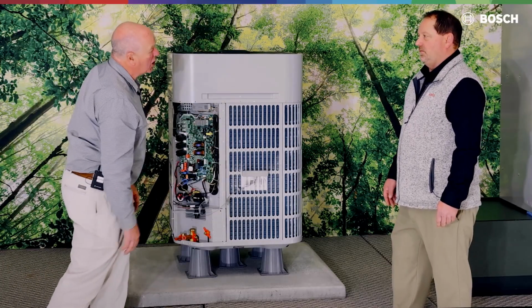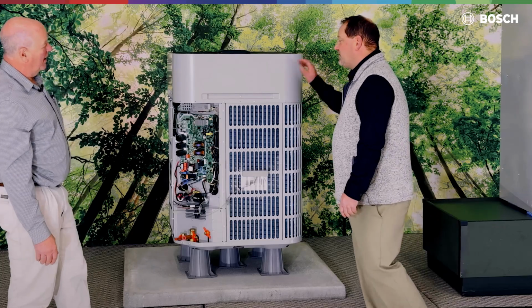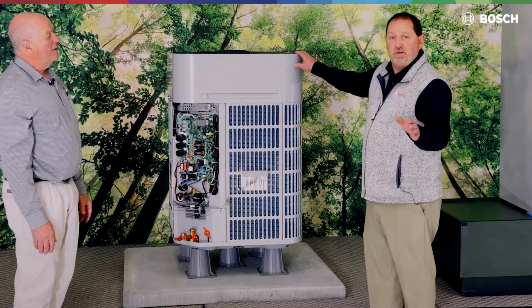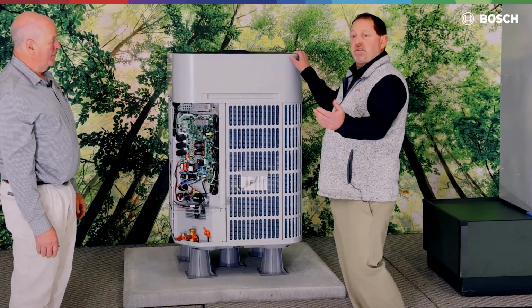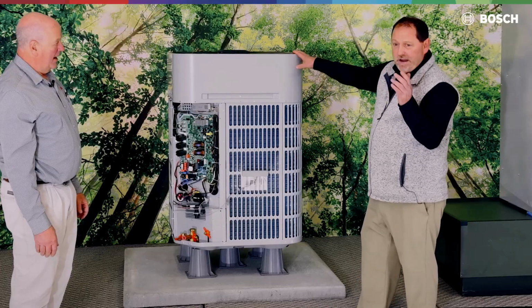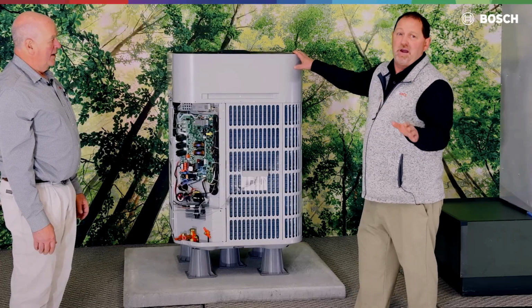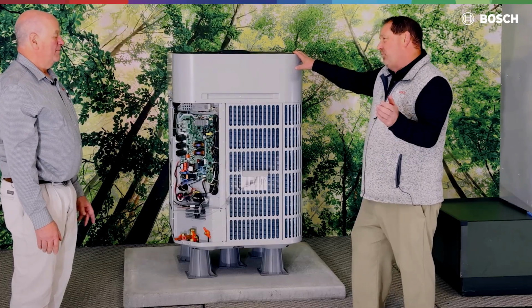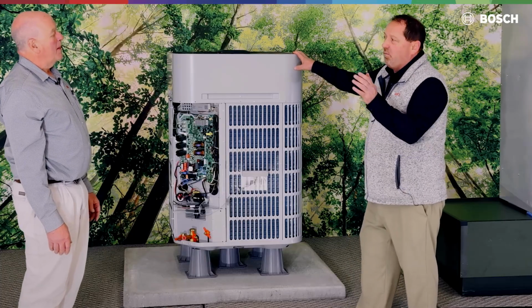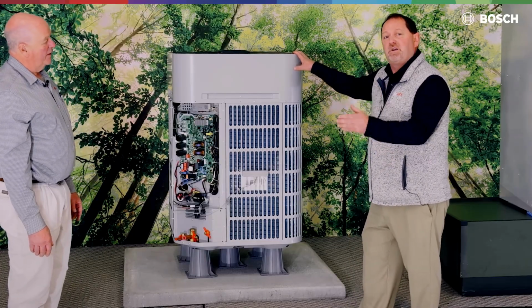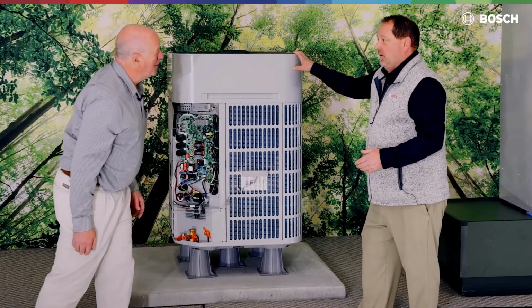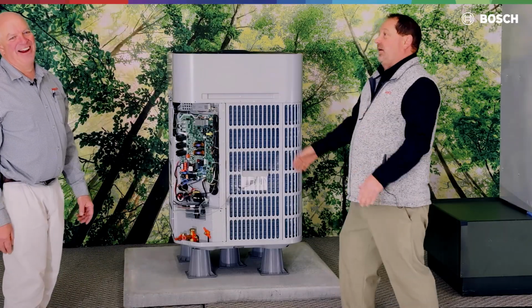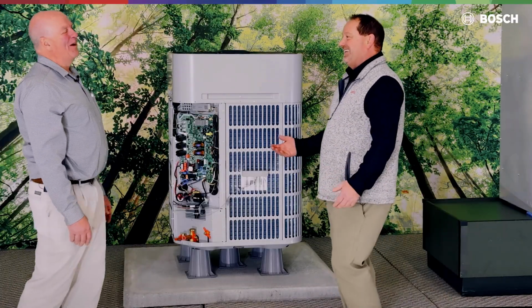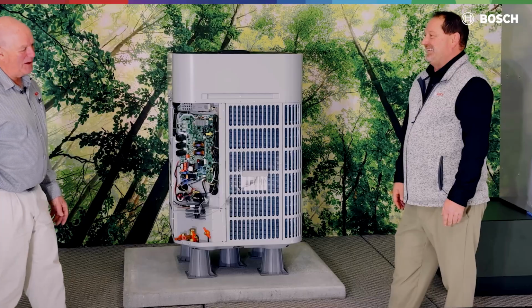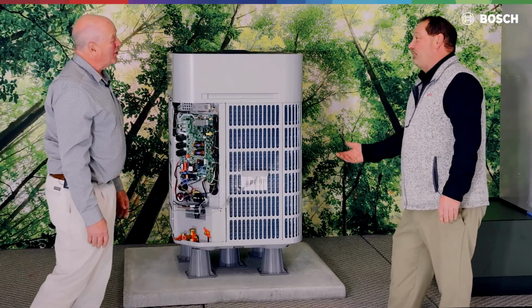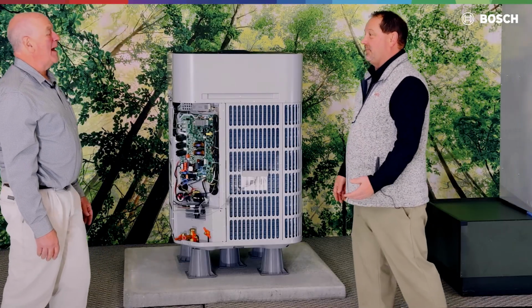And Chris, what is our charge add going to be per foot? Well, this particular product comes pre-charged for 15 foot of line set. Since we just installed this, let's say 150 foot, we need to add 0.6 ounces. I think the manual actually says 0.59. 0.6, splitting hairs here, 0.6 ounces per foot after the initial 15. So how many ounces would that be, Chris? Well, I'm going to go with a 150-foot line set. We're going to subtract the 15 foot from the 150, which brings it down to 135. 135 times 0.6, we're coming to about 81 ounces of refrigerant.